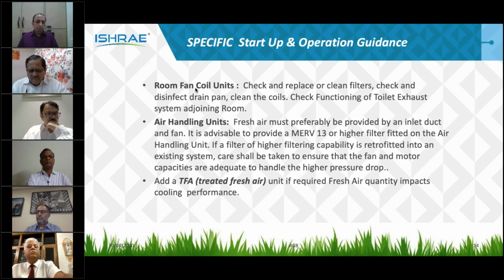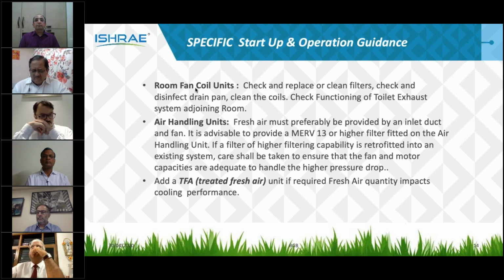Now coming to the air handling units, which are of particular concern because these ducts go all over the place, there we are advising that you should go for a filtration rate of at least MERV 13. It's a particular grade of filter. If you compare it with the normal filters that are installed, it is a far superior grade, so that the filtration can at least take care of most of the pathogens that are in the air.